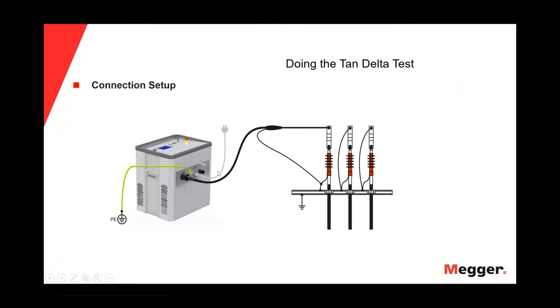Okay, talking about the connection setup for the tan delta test, in this case we're seeing our VLF Sinus 45, which has an internal tan delta, so the connection setup is very easy, very friendly. We have only our safety ground, the high voltage cable, and the power cord. Okay, very easy to connect this unit.